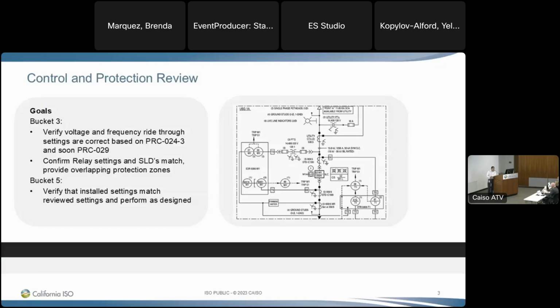For control protection, the goals are to verify things like frequency, voltage, and frequency ride through. It used to be PRC 24, which still applies today, but it's soon going to be PRC 29, I believe by October of next year. We confirm relay settings and the single lines match, and that we have overlapping zones with no gaps in the protection. For bucket 5 control protection, we're just verifying what you submitted was put in the field and still meets the requirements.